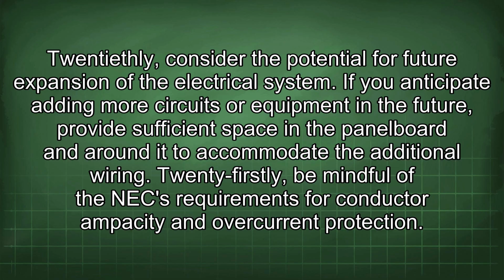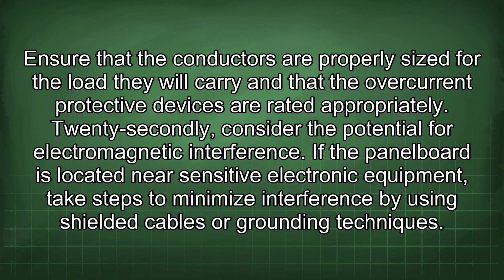21stly, be mindful of the NEC requirements for conductor ampacity and overcurrent protection. Ensure that the conductors are properly sized for the load they will carry and that the overcurrent protective devices are rated appropriately. 22ndly, consider the potential for electromagnetic interference.